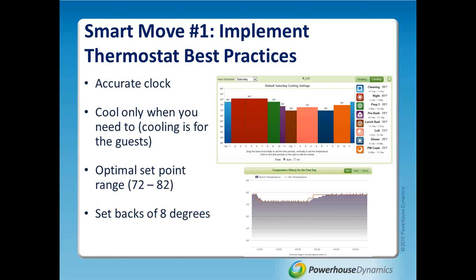What we ask our clients to do is map out when the peak demand hours are, say the lunch crowd and dinner crowd, and modulate their temperature set points. Generally most clients keep their spaces in the 72 to 74 degree range for occupied times, then bump it up to 82 to 85 degrees when unoccupied after hours, about an 8 to 10 degree setback spread.